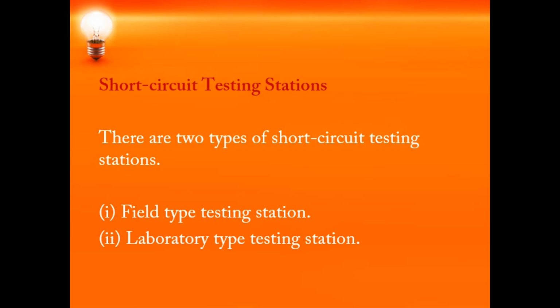Whereas in the laboratory type testing station, you will have a setup. That setup and equipment will be meant especially only to test a circuit breaker. So what you can do, you can keep on testing the circuit breaker n number of times, okay, or you can test different circuit breakers. You can take a whole day to test the circuit breakers, no problem. But what will be the disadvantage? The disadvantage is the initial setup cost, no? That will be very high, and you will not have a large power to test a circuit breaker. You will have a limited power to test the circuit breakers.